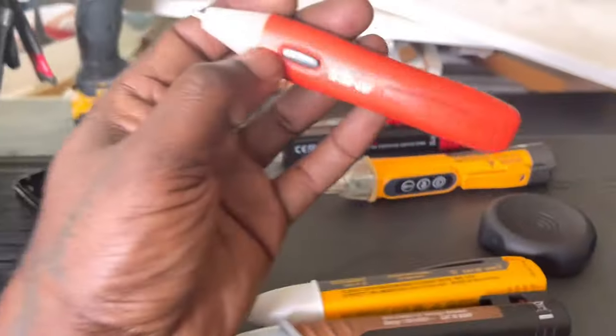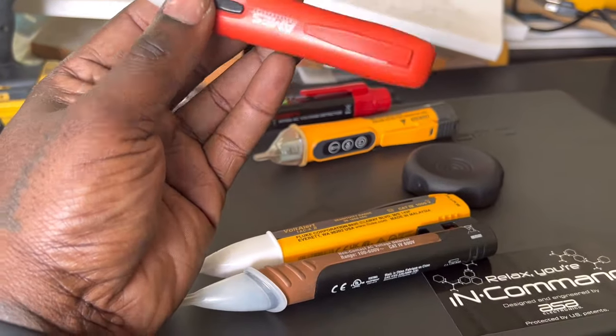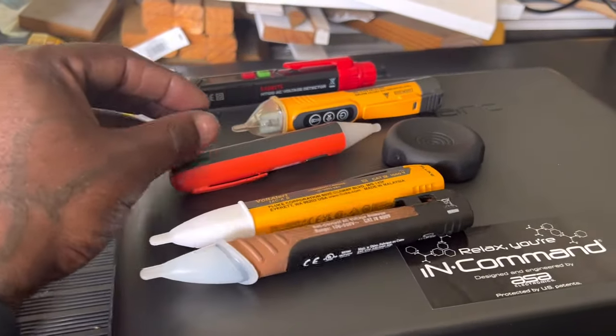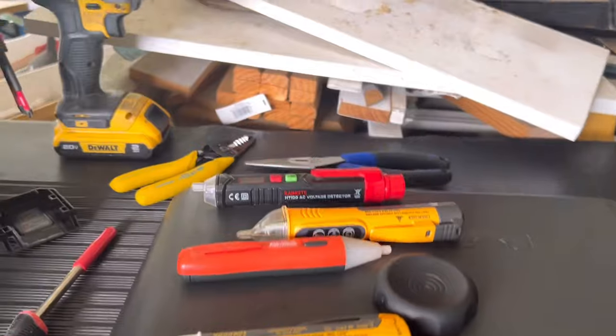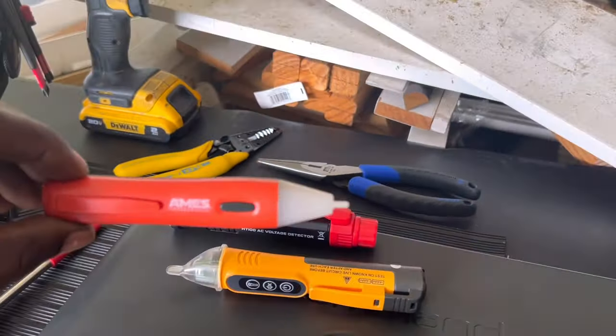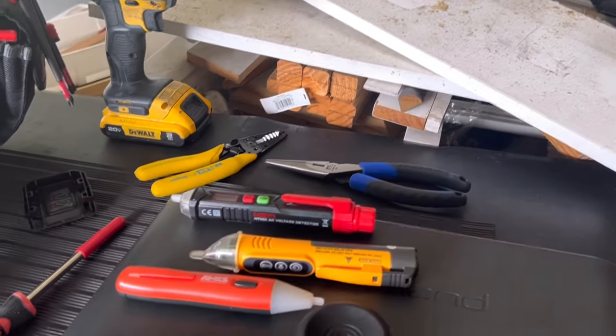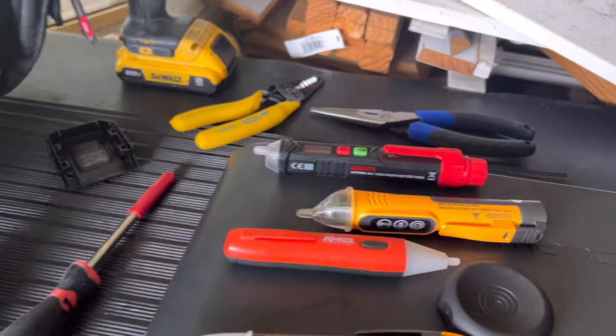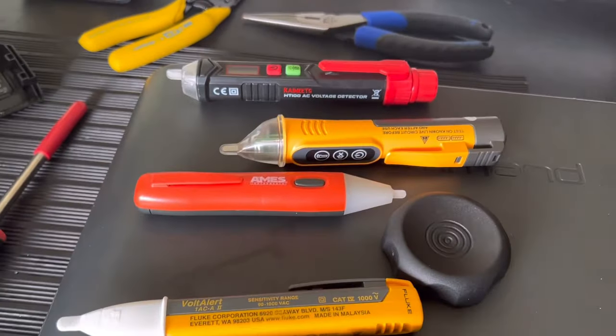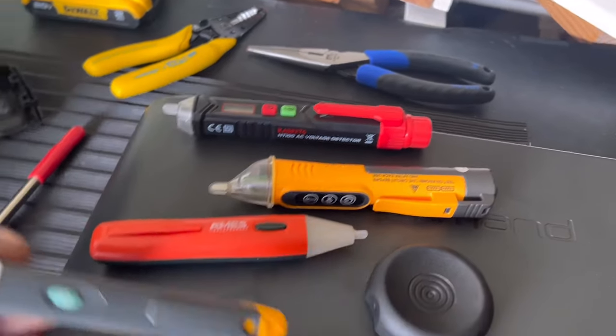That's the drawback to the Ames. For safety purposes — checking if something is hot — it's very good for a hot skin test because it will pick up low voltage and is super sensitive. It's a good choice specifically for a hot skin test.